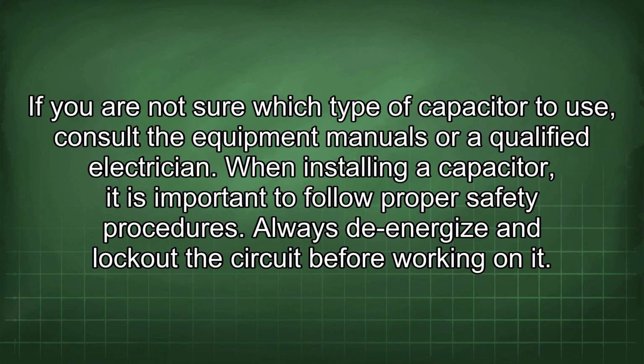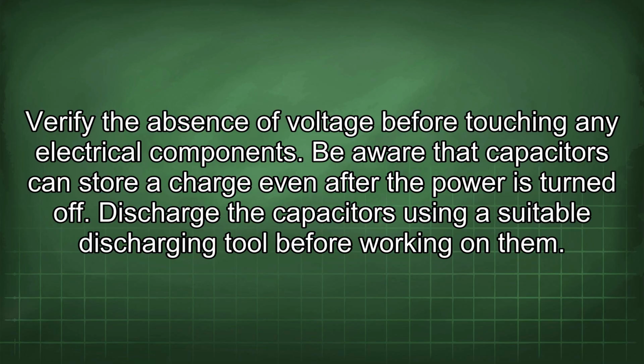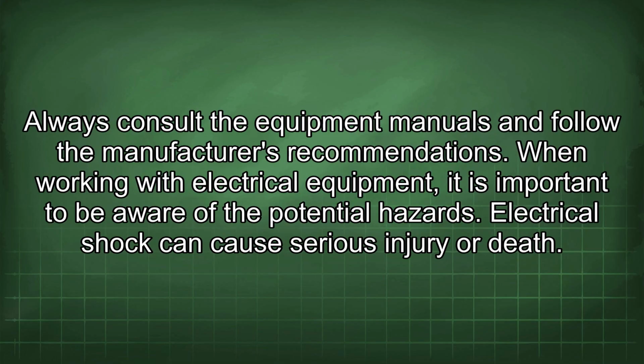When installing a capacitor, it is important to follow proper safety procedures. Always de-energize and lock out the circuit before working on it. Verify the absence of voltage before touching any electrical components. Be aware that capacitors can store a charge even after the power is turned off. Discharge the capacitors using a suitable discharging tool before working on them. Always consult the equipment manuals and follow the manufacturer's recommendations.